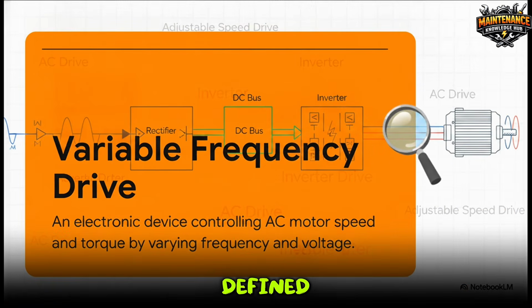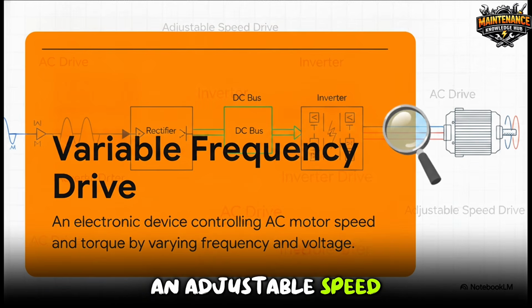So, formally defined, a variable frequency drive is an electronic device that controls the speed and torque of an AC motor. And how does it do that? Literally just by varying the frequency and the voltage being supplied to it. Now, you might also hear this technology called an AC drive, an inverter, or an adjustable speed drive out in the field. Don't let that confuse you. They all fundamentally mean the exact same thing.